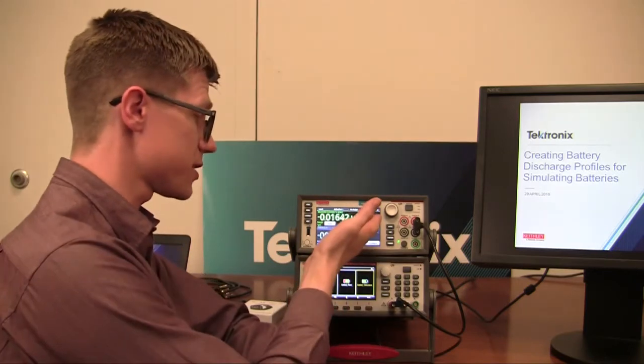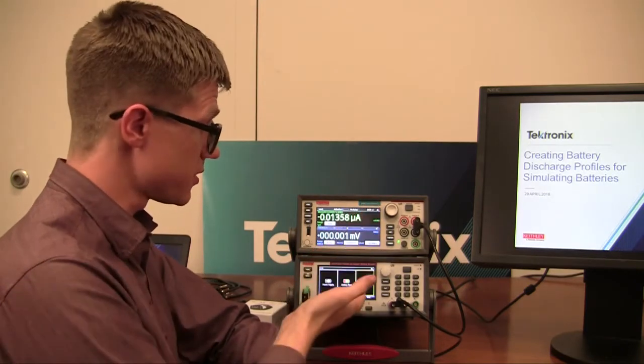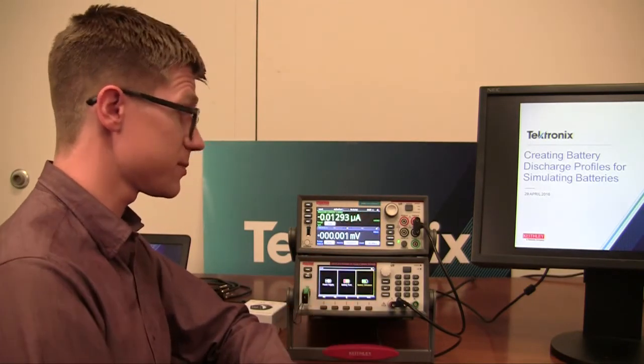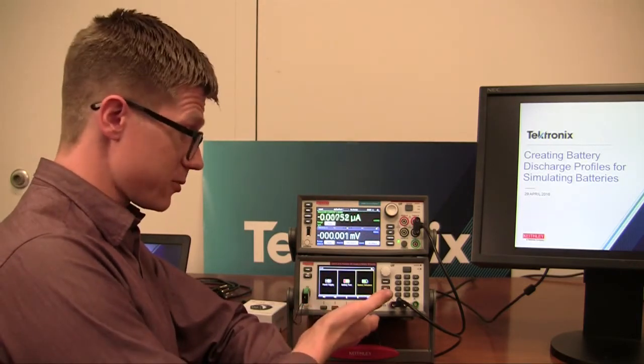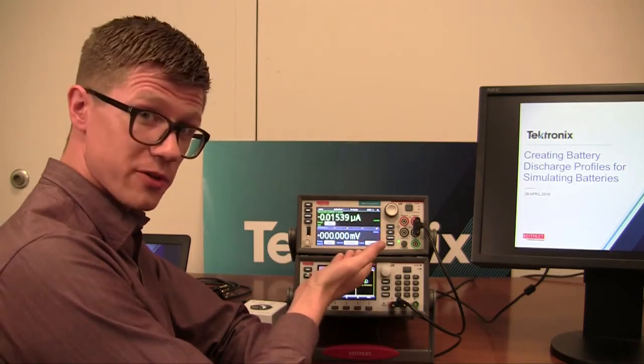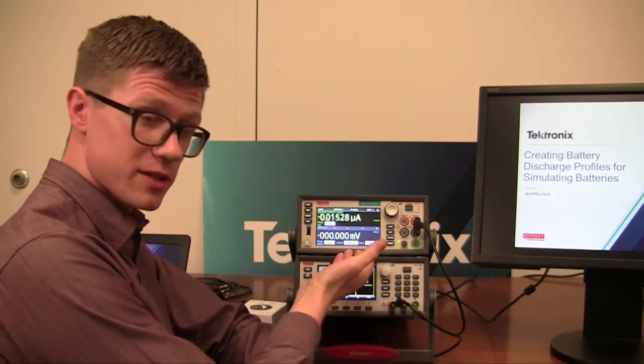So essentially what we're going to do is connect the 2460, in this case, to the 2281S Precision DC Supply and Battery Simulator. We're going to simulate a battery with this one and then discharge the battery with this and create a model of it.